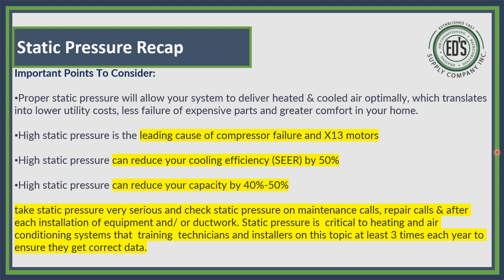Now, these are important points to consider, and we went over this just a while ago, and I'm going to slow it down just a little bit more to recap this. But proper static pressure will allow your system to deliver heated and cooled air optimally. If you have less resistance, your furnace doesn't have to work as hard. I don't even know if that's proper English, but it's not going to run as long.